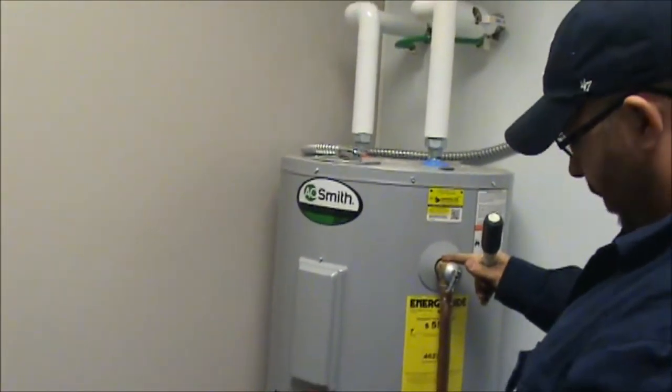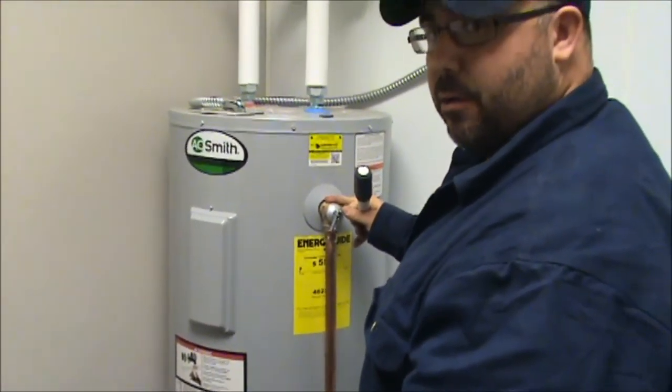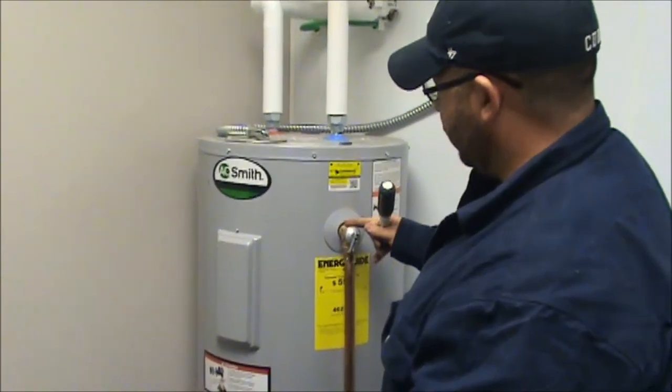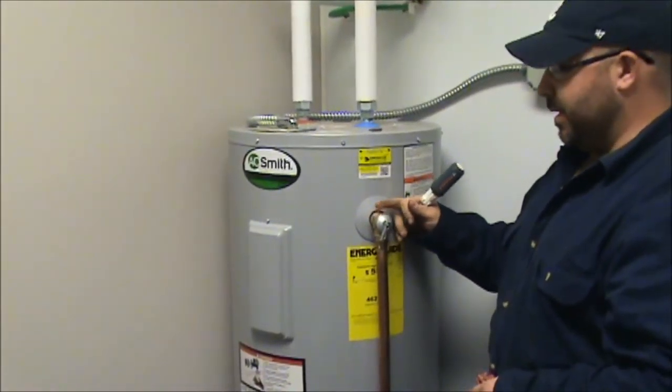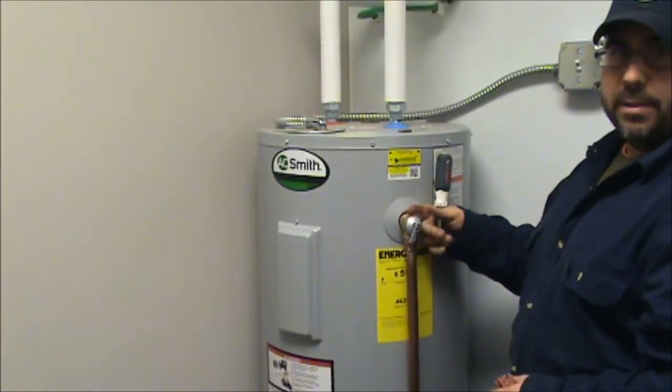It's your T&P valve. It will only leak water if it gets too hot or it builds up too much pressure. If it's dripping, it means it's doing its job. If it keeps on dripping, we have to replace it. No big deal.